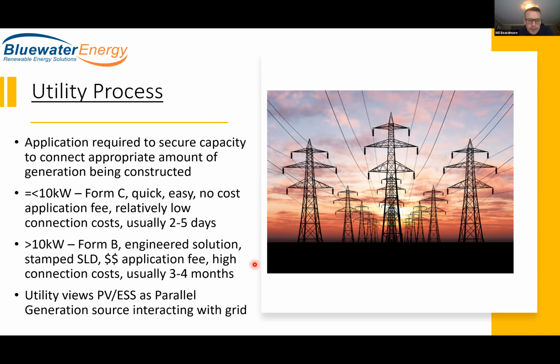There's a cost for the Form B application, which can be as high as $5,000 or $6,000, and connection costs we've seen range from $6,000 to, depending on the size and capacity of the PV system, north of $200,000. So there needs to be real benefit to the actual PV system in order to justify these costs.